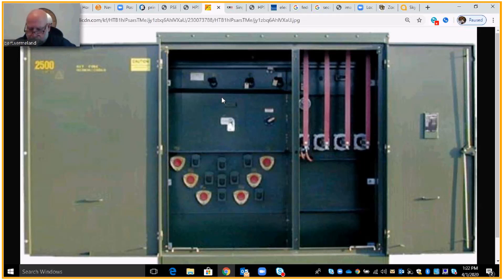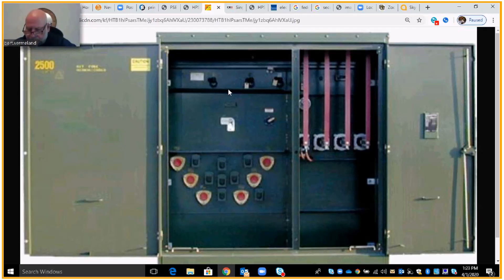Another property of this transformer: it is fused — one, two, three fuses, one for each phase. These are called bayonet fuses, similar to a bayonet at the end of a gun. They are the fused portion for the transformer core and windings. If there's a fault inside the transformer case, or on the secondary lines — say someone digs in and causes a short — these fuses will blow. Simply take your shotgun stick, open the fuse, pull it out, replace it, put it back in, and you restore power to the secondary.